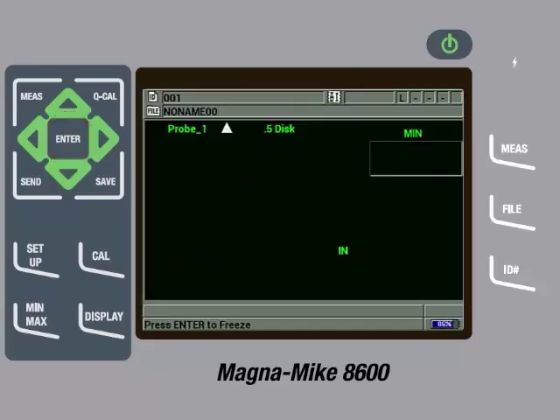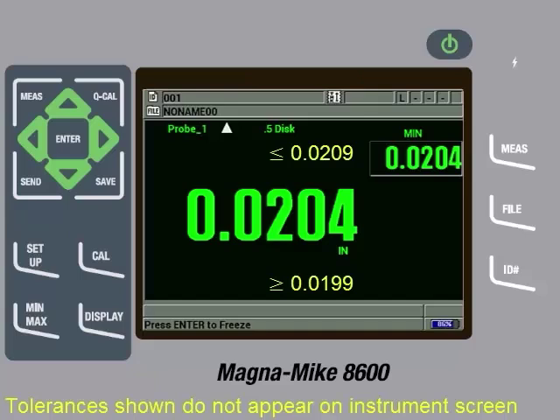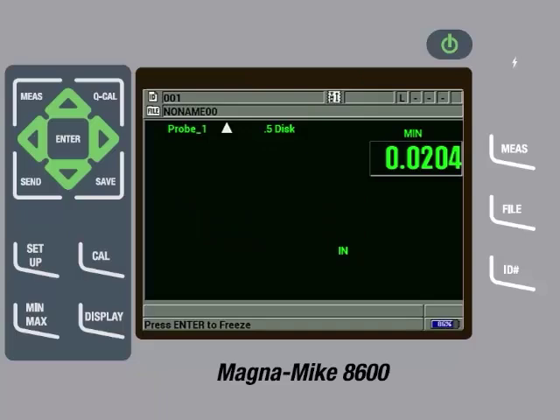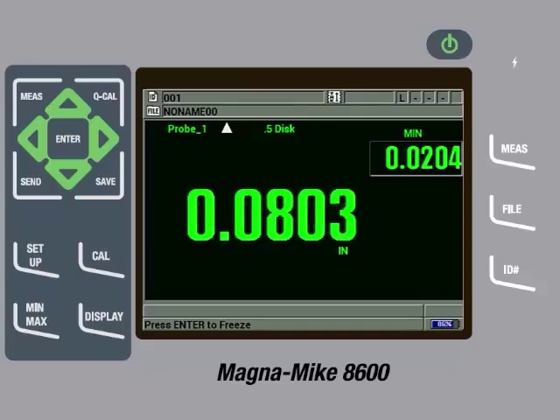Whenever you recall a calibration file, it is always recommended to remove the target from the probe tip and perform a QCal by pressing the QCal key. It is also good practice to then check a few reference standards to make sure the instrument is reading within specification and a new full multi-point calibration is not needed. We will check the 20 thousandths of an inch shim to make sure it is measuring within specifications, which it is. Then we will check the 80 thousandths of an inch shim to make sure it is measuring within specifications, which it is.